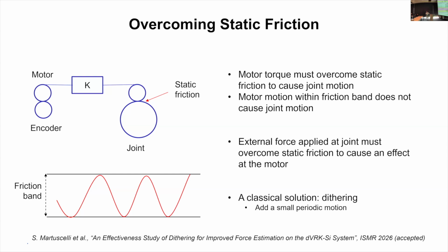One of the things we're looking at is even using a dithering approach. I have a paper coming up on that at ISMR. The idea being that you've got this static friction, so you have the case where the motor and encoder could be saying, hey, I'm moving, but in reality, nothing's happening. And conversely, if you apply a force out here to the friction, you measure nothing here until you break the static friction. So by using this dithering, where you're constantly doing a low amplitude oscillation down here, this is a technique that dates back probably at least 50 years, if not more. You can try to essentially minimize the effect of that friction band.